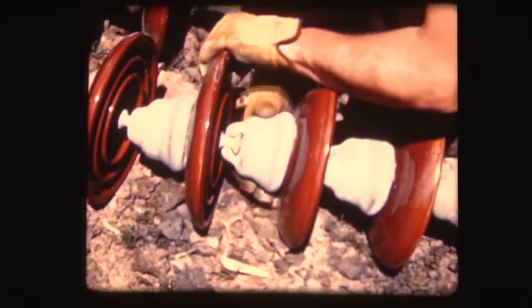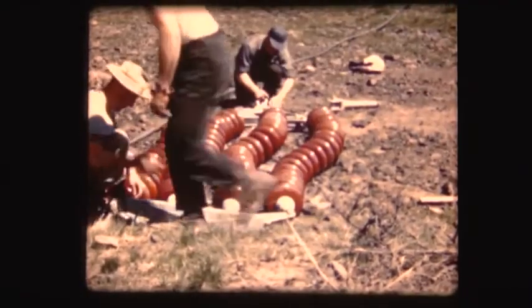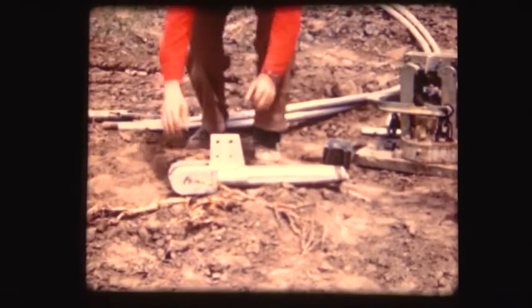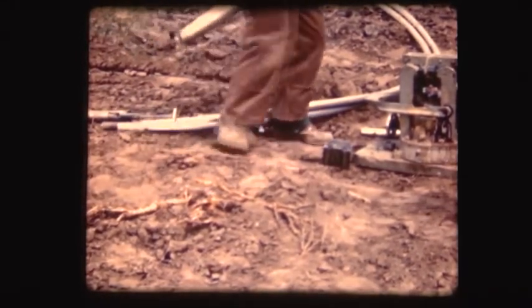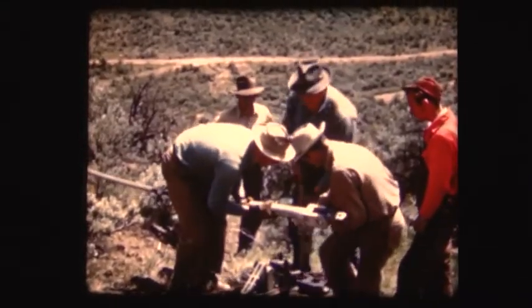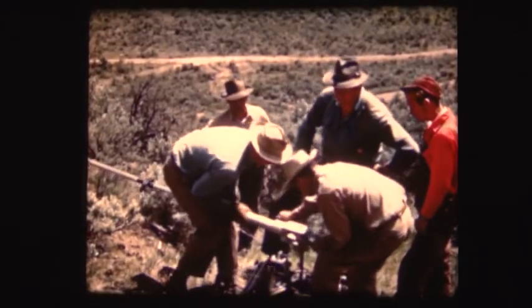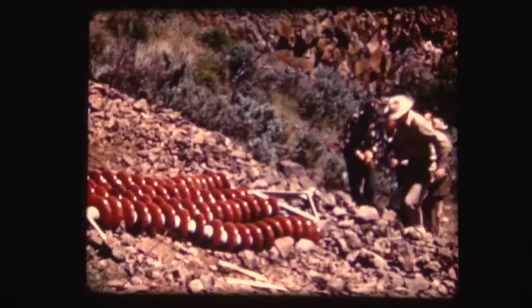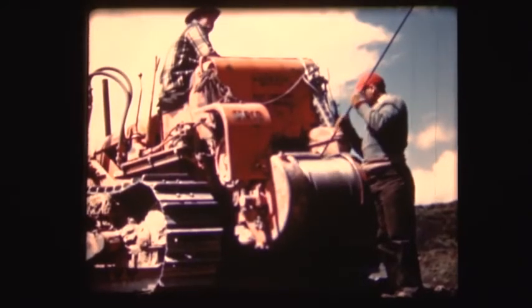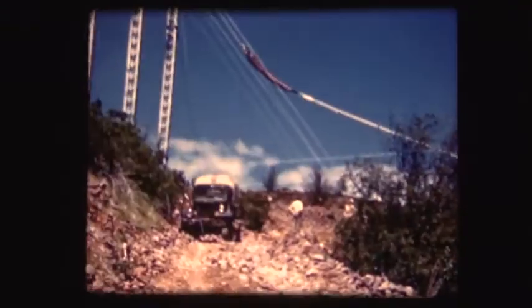Insulators, designed to meet the electrical and mechanical requirements of the particular situation, are assembled. Again, compression fittings are used. Steel and aluminum dead-end bodies, similar to the compression joints used on splices, secure the end of the ACSR conductor to the insulator string. They are pressed on in the same way. The dead-end body has a clevis end for attaching it to the insulator string. The usual procedure is to hoist the entire dead-end assembly, conductor with dead-end fittings and insulators, at one time.